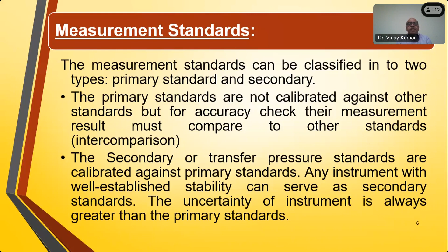But a secondary standard needs to be calibrated against the primary standard, and these are used to transfer the observation, to transfer the data from primary to secondary, and to serve the purpose of calibration down to the floor level, the ground level. The uncertainty of the primary standard is smaller than that of the secondary standard. So here I mentioned some pressure measuring devices. There are three categories of pressure measuring device. One is manometer, another is mechanical gauge, and the third is electronic pressure gauge.